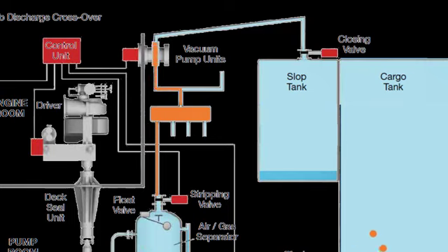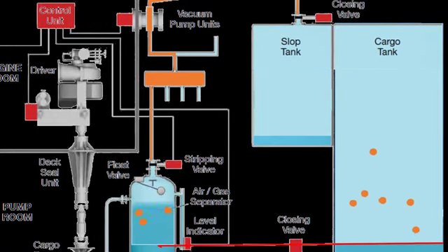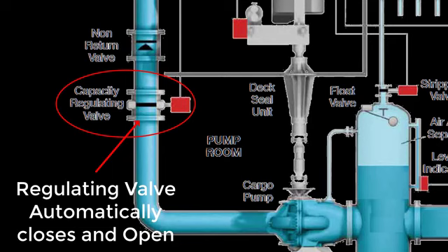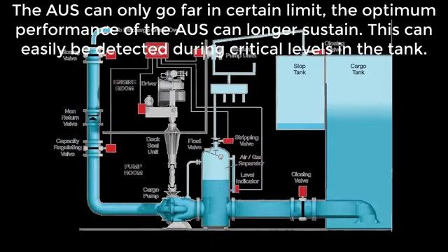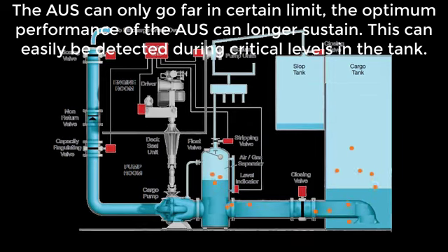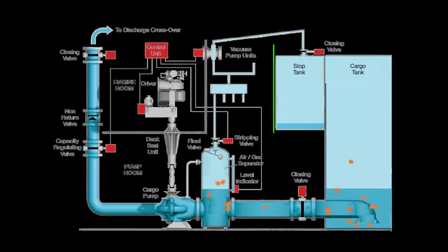At the same time, if, during the AUS process, the separator tank is filled up due to high volumes of gases, then the capacity regulating valves close or throttle down a bit to build up high suction pressure, helping the separator to be filled up and sometimes minimizing cavitation within the impeller. This goes on and on as long as the pump is still stable. The gases or air and some liquids are directed to the slop tanks. Eventually, the chief officer may take off the AUS and do the manual throttling of the capacity regulator valves.